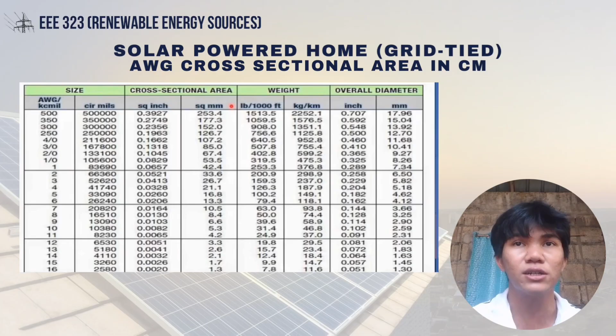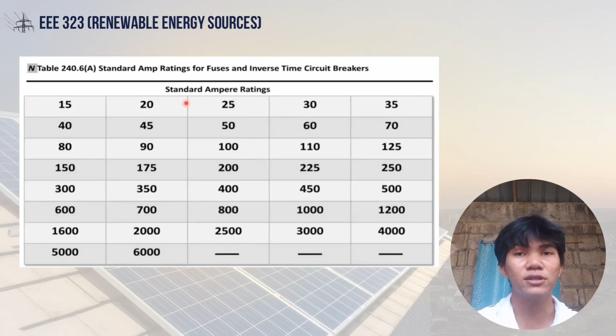Another table, 240.6(A), standard ampere ratings for fuses and inverse time circuit breakers. Dito po nakabase yung standard ampere ratings ng fuse and circuit breakers na pwedeng gamitin sa solar power system. Sa steps in PV system conductor sizing, dito na malalaman kung anong size ang pwede nating gamitin sa pag-install ng wire sa solar power system natin. First, look for the ISC rating of the photovoltaic cell.